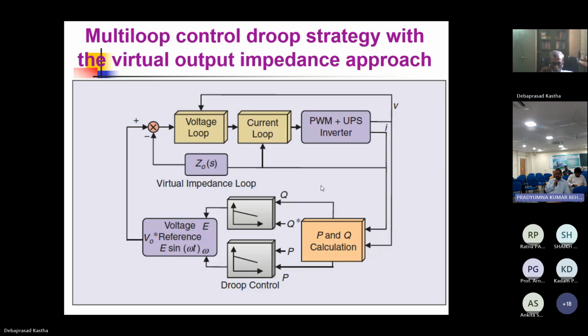Regarding how that virtual impedance is implemented: it is just a calculation. It is just calculation software in the inverter system. There is actually no impedance. So you take I0, and then say if there was an impedance Z0 at the output of your inverter, how much drop would have been there? You calculate that drop and subtract it from your reference voltage, just to compensate for that droop. Yes, droop compensation. Okay, sir, I got it. Thanks, sir.